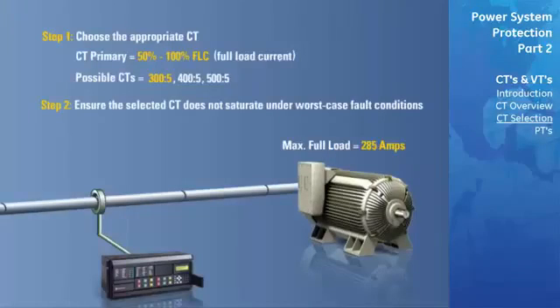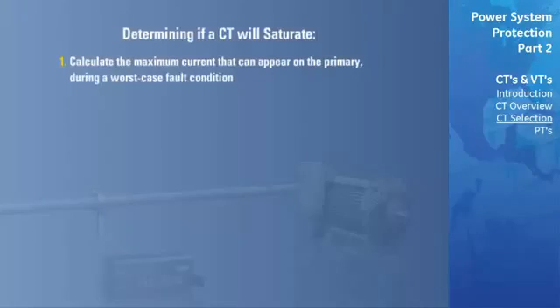The next step is to ensure this CT doesn't saturate under worst-case fault conditions. If it does, a higher ratio CT, such as the 400 to 5 CT, may need to be chosen. The first step in determining whether a CT will saturate is calculating the maximum current that will appear on the primary of the CT under a worst-case fault condition. The maximum fault current at the load is determined by a fault study, and in this case was determined to be 6,000 amps.